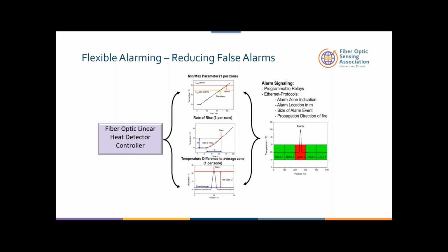What I would like to point out is that if I go to buy a conventional linear detection, I have to know in my mind if I'm buying a 155 degree Fahrenheit, 145 or different Fahrenheit system. In the case of fiber optic, you don't need to know which system you buy. You literally are buying a fiber optic UL rated cable with the controller, with the ability to change these parameters based on a lot of different things, it could be a regulation, but it could also be the ability to say, based on what I understand and what I've done in the test, I can change this alarm based on what I've seen.